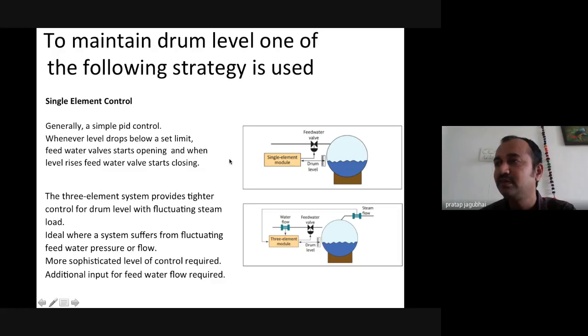Drum level control widely uses 3-element control. Why? I will say right now. Single element control is only the level measurement. This level is basically, as you know, P equals h rho g: pressure equals height multiplied by rho, which is density, and into gravity. Rho and g are constant, so pressure is directly proportional to the height or level.